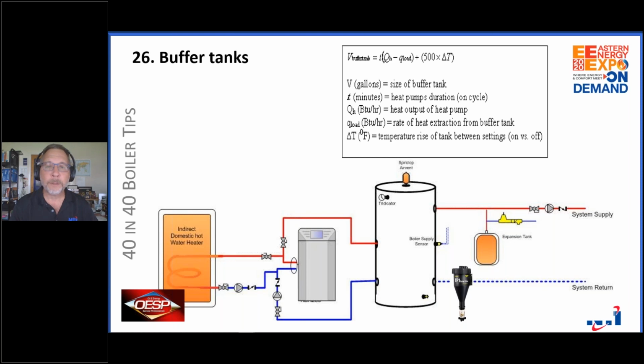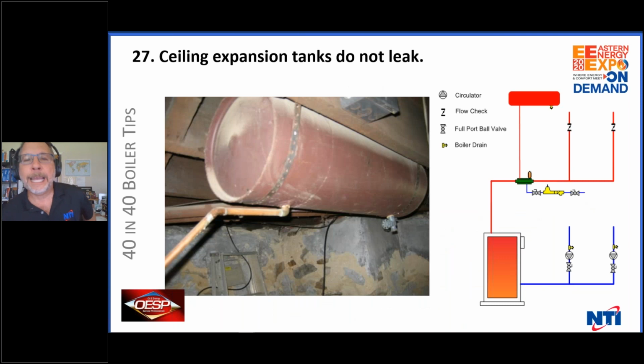Believe it or not, the proper size buffer tank is not always 40 gallons. I've sized them to as little as 10 gallons. I've sized them as large as 120 gallons. Size them correctly, use the formula. Ceiling expansion tanks don't leak.